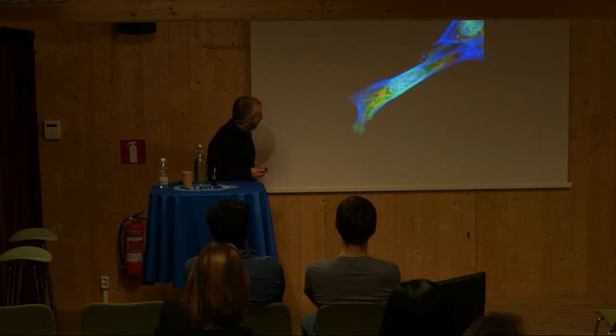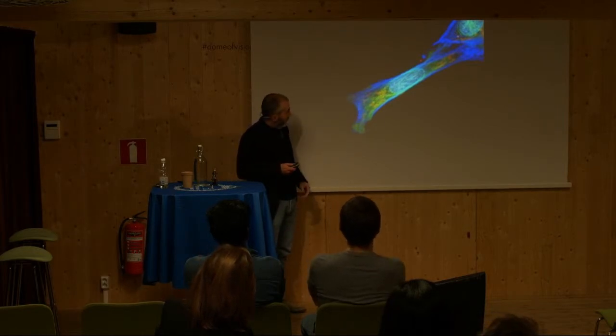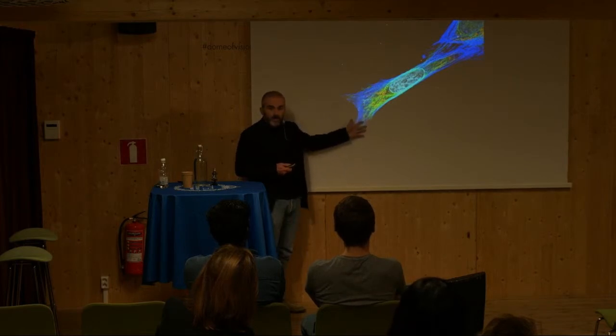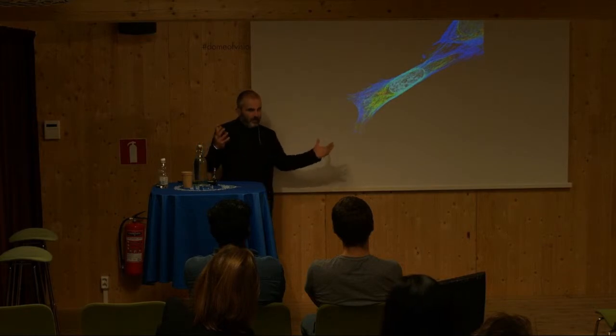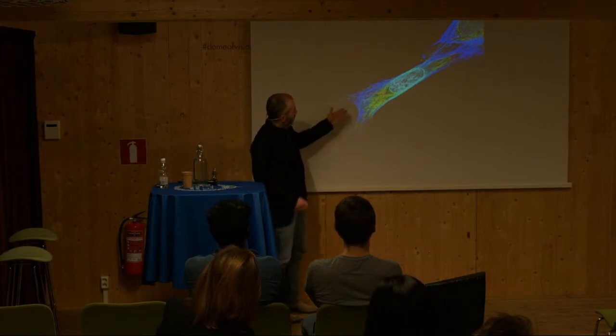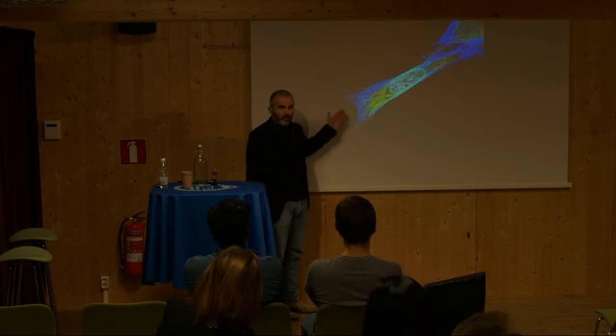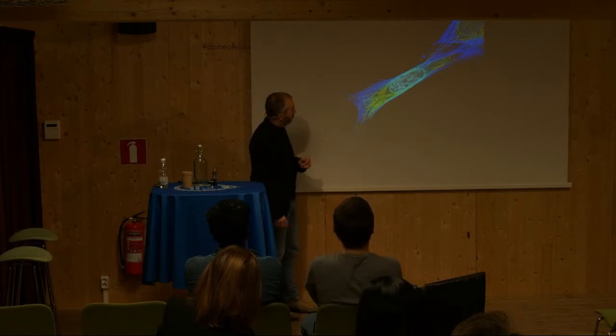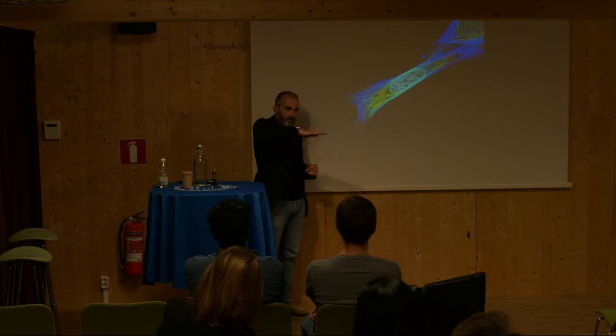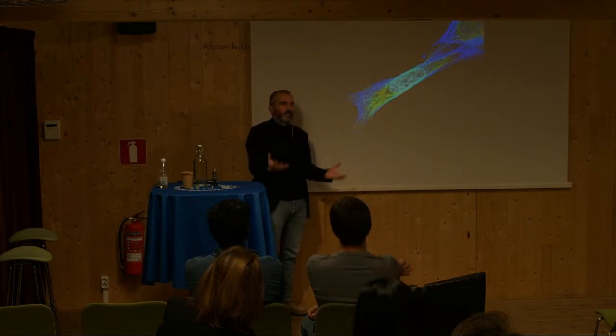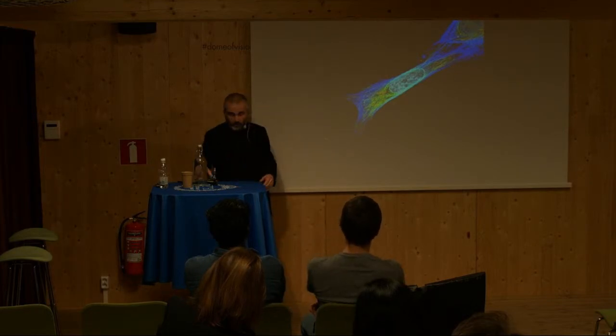What happens in the confocal microscope? You see the blur in the normal fluorescence image, then turn on the confocal microscope and you see the details — it gives higher resolution. It takes away everything that is out of focus, so we only see what is in the focal plane of the microscope. We do optical slicing, looking at thin layers of a 3D object, and can then record a full three-dimensional volume and create 3D images.